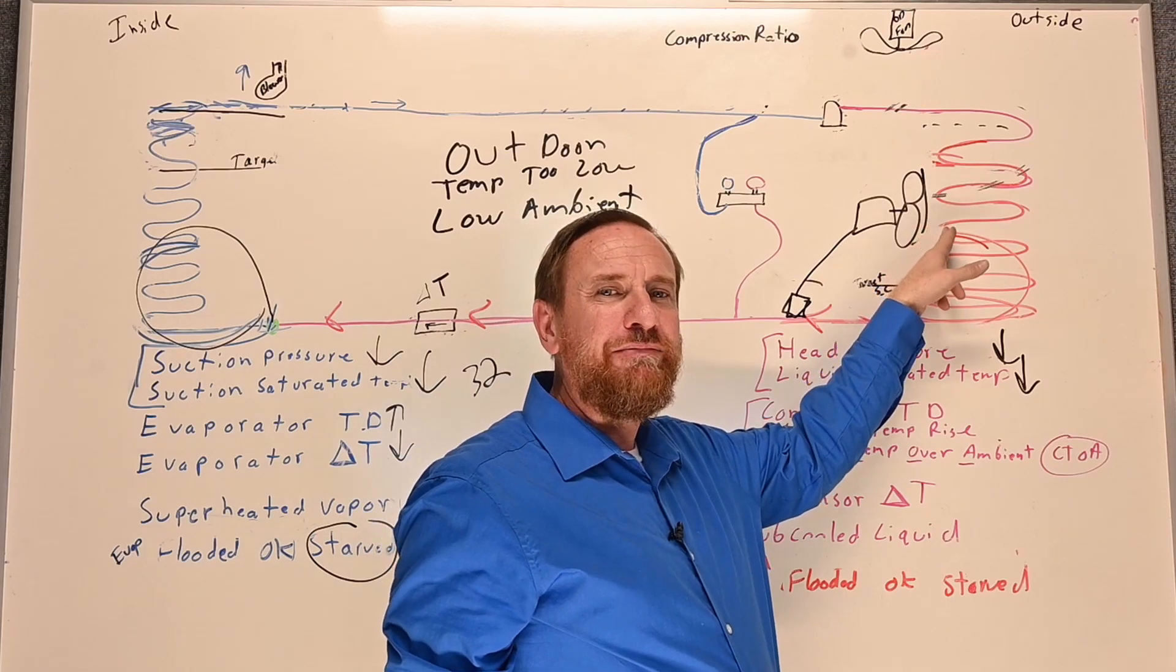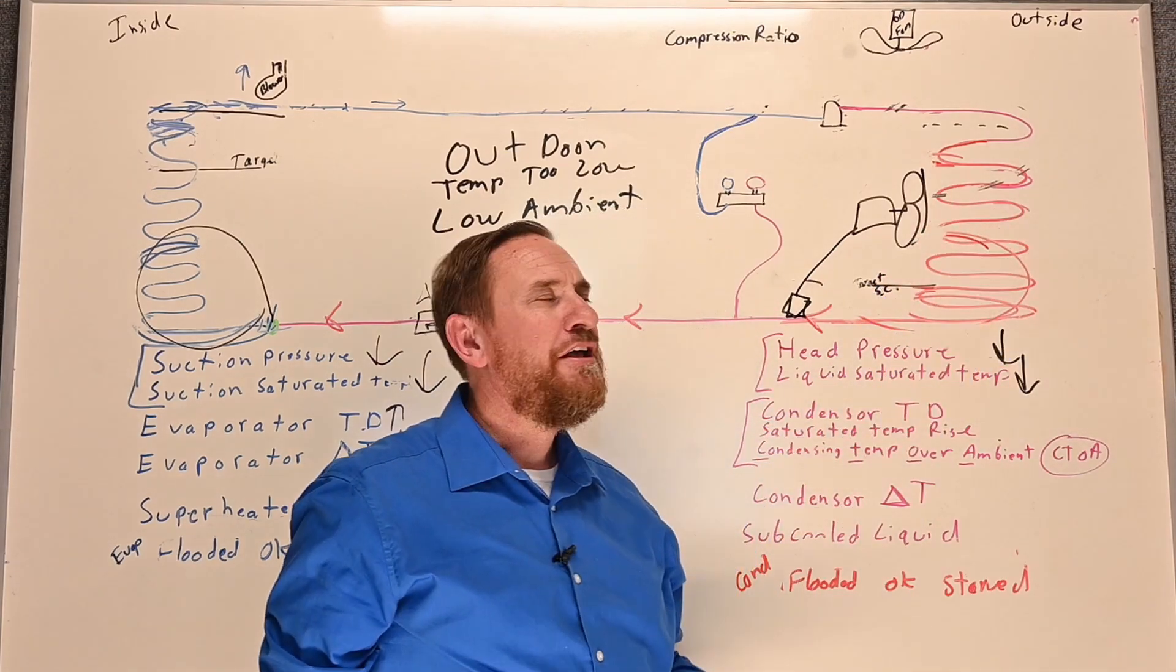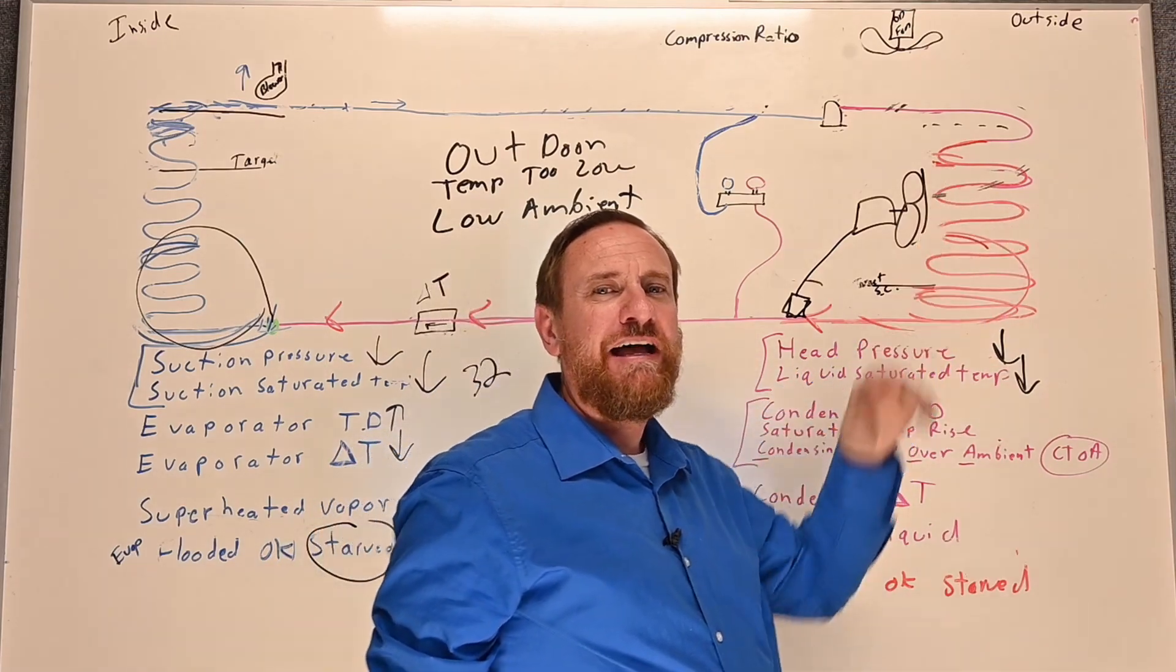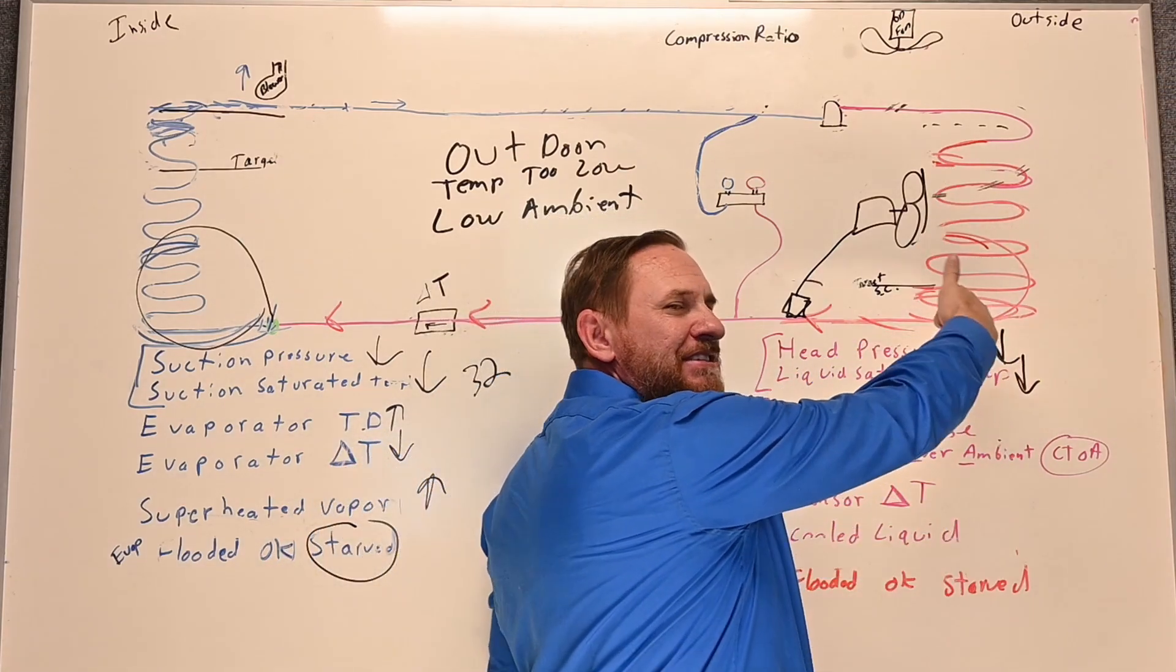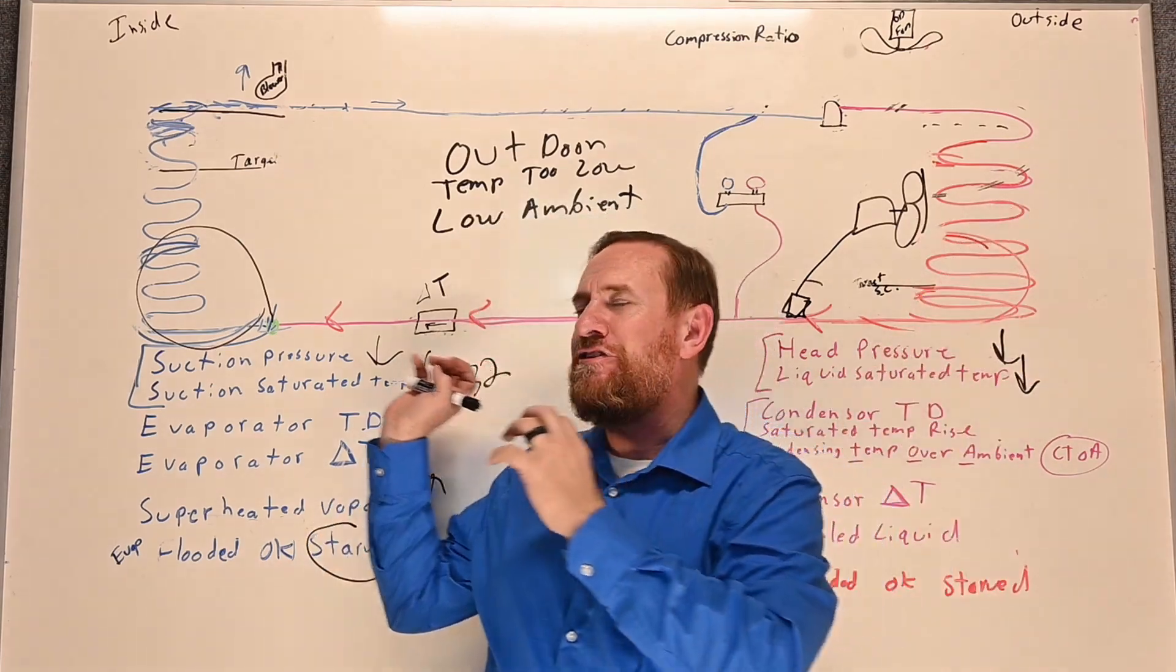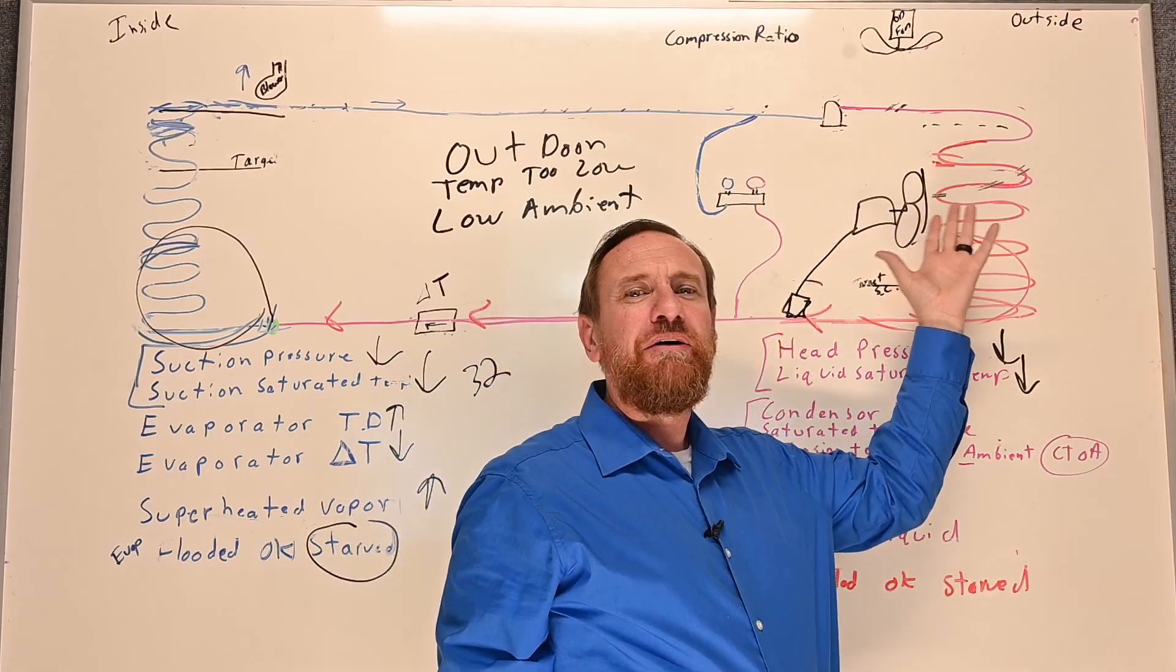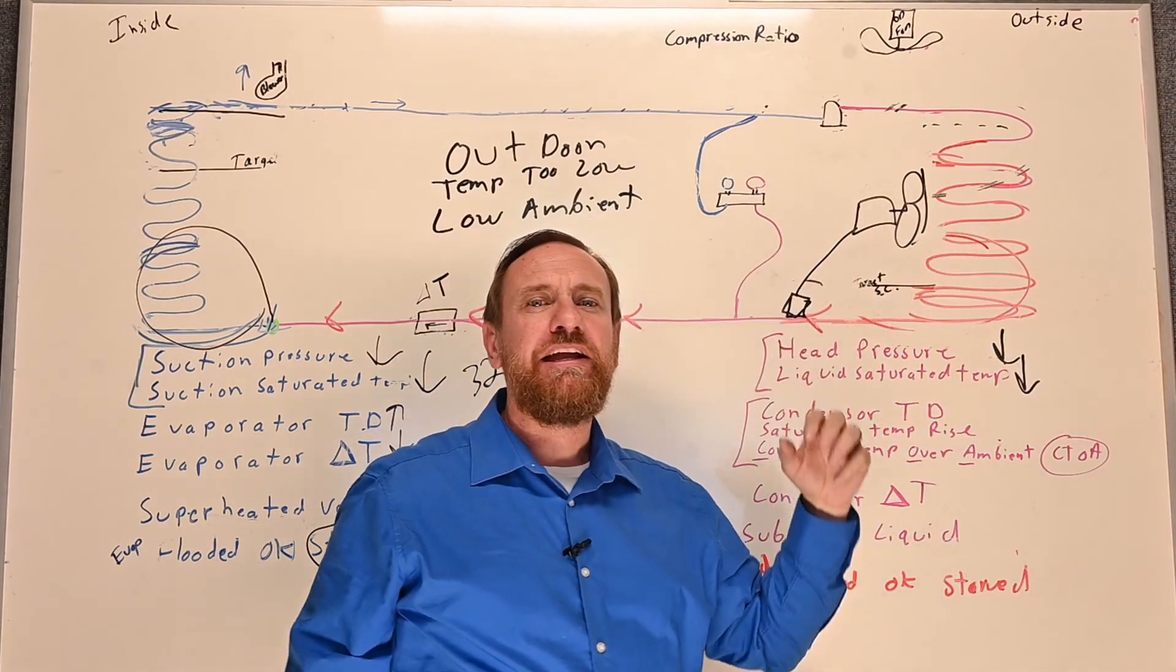But if I shut this fan motor off, I'm now moving less heat across that condenser coil. By moving less heat across the condenser coil, my head pressure is now starting to go up and my liquid saturated goes up. Now I'm pushing enough refrigerant in my evaporator coil that all of this starts going back in the range. But we can control our head pressure with a low ambient kit.